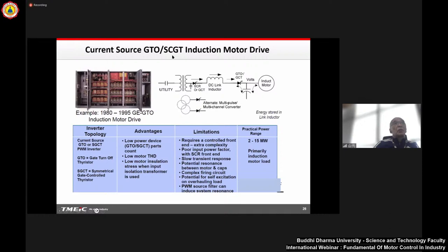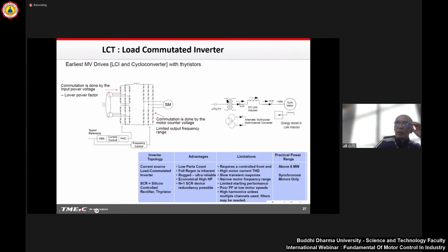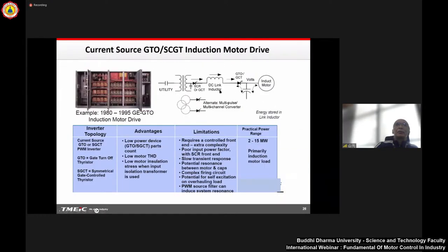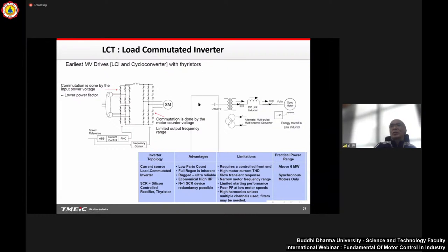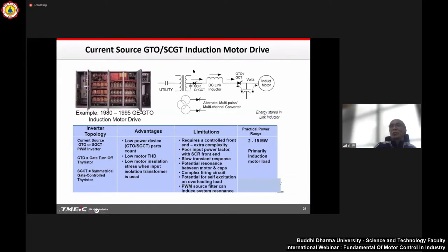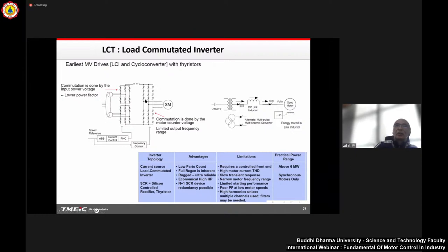The current source GTO/SGCT induction motor drive is similar to the current source LCI - the input current control is the same, using thyristor or GCT. But the output driving the induction motor needs to apply a self-switching device like GTO or GCT. You may study later the difference between LCI and this induction motor drive: LCI needs to apply synchronous motors, not induction motors, because LCI uses thyristors (SCRs), which cannot be controlled for off-timing by the gate.